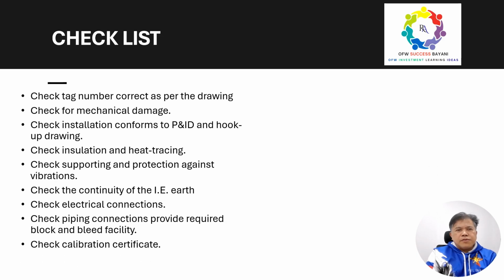So this is the checklist for your idea, and maybe some of you are encountering for the first time how we proceed with the inspections based on our checklist, where we do the verifications for our transmitter. Okay, so check the tags are correct as per the drawing. So we have an approved drawing. So verify the tag, is that correct? So check the mechanical damage and any damage to your device. So crack or maybe something broken.